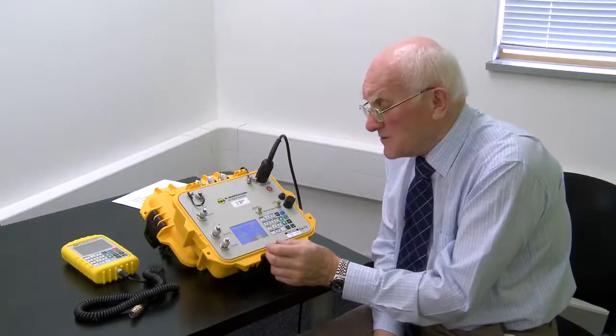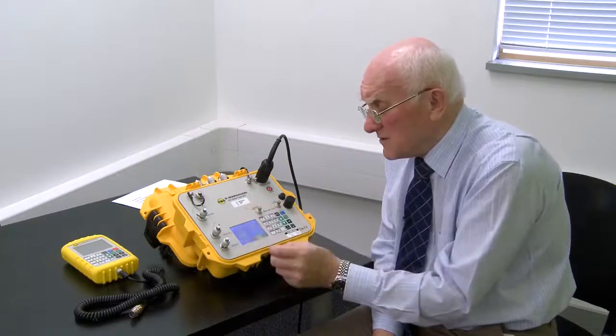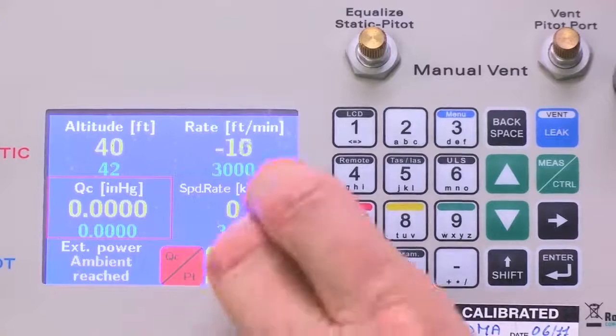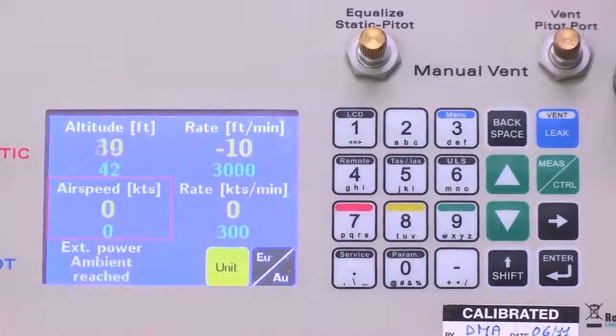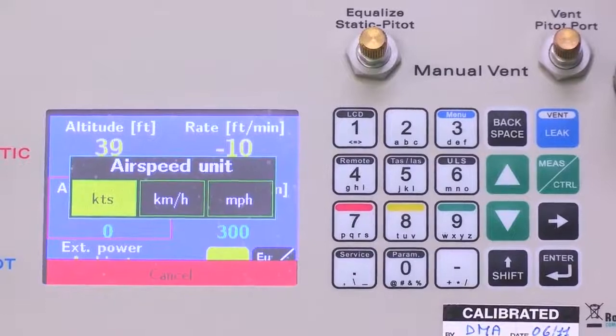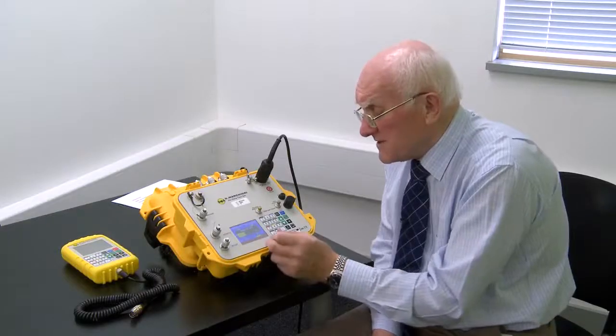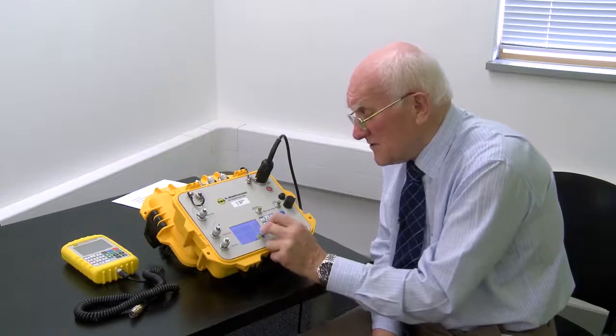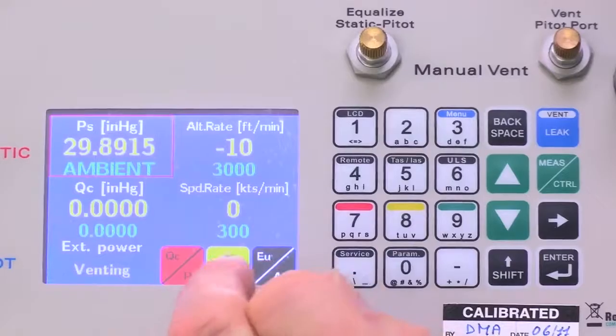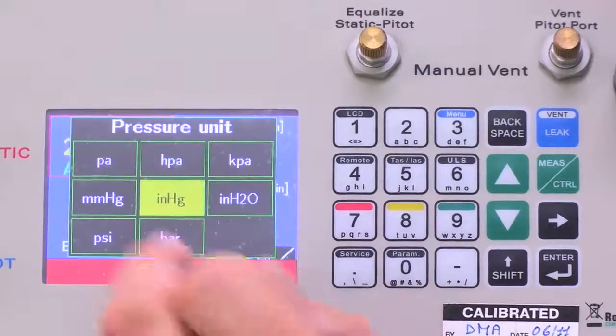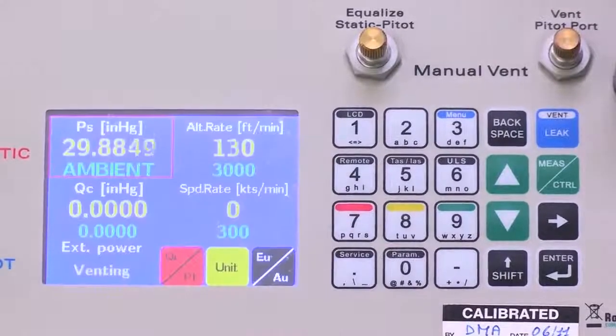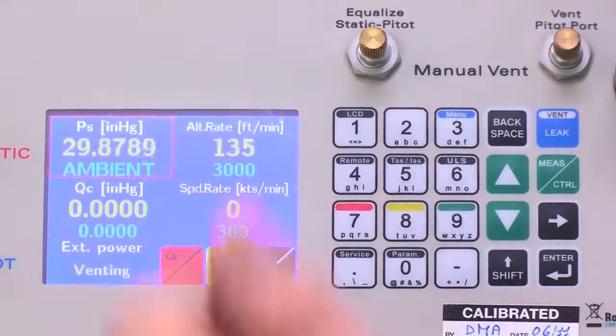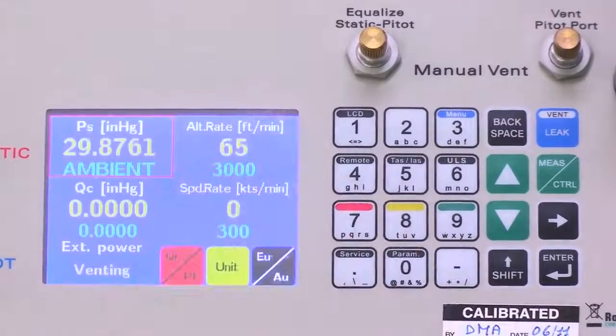If we want to change from aeronautical units to engineering units, we go to the value we want and select the units. It tells us the airspeed in knots, kilometers per hour, etc. But we want engineering units and decide which unit we'd like, for example inches of mercury. Now instead of the PS channel being in feet, it's in inches of mercury.